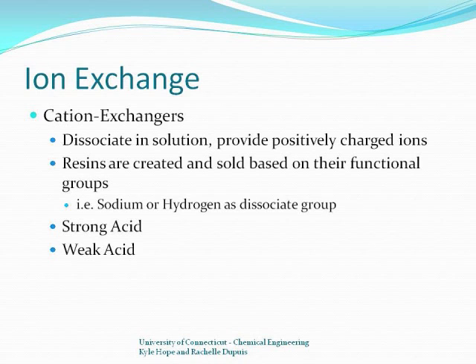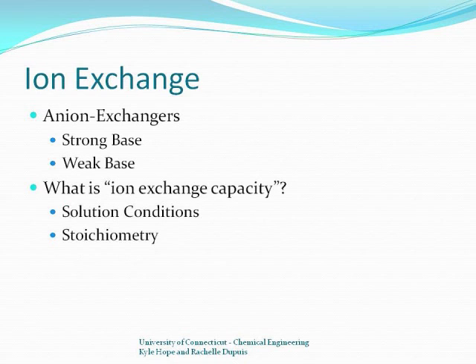Strong acid cation exchangers have an exchange capacity that is independent of solution pH because they dissociate well. Exchange capacity refers to the amount of ions a resin can exchange before being exhausted. Since ions are exchanged in a chemical reaction that follows the laws of charge balance, if we want to get rid of an ion like calcium with a +2 charge and replace it with a +1 charged sodium ion, we'll need two sodium ions for every calcium ion. This means two sites on the resin polymer will be exhausted for every molecule of solution that passes through it.